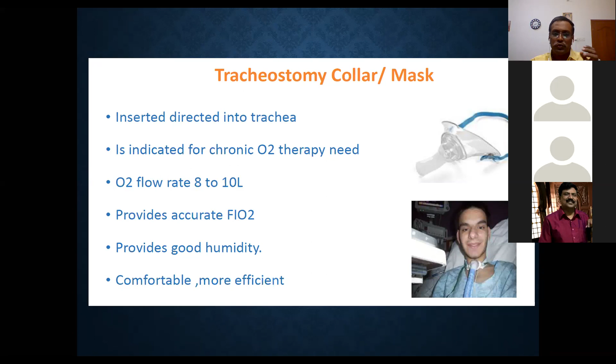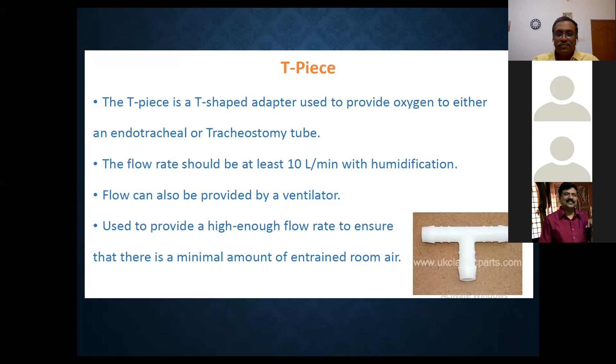And the next one is a T-piece device. We can use this in an intubated patient. Before extubation, we can give a trial of spontaneous respiration to assess the ventilatory effort of the patient and whether the patient is able to maintain saturation or not. It is one of the weaning modes for oxygen therapy. The T-piece is a T-shaped adapter used to provide oxygen to either the endotracheal tube or a tracheostomy tube with a flow rate of 10 liters per minute. Flow can also be provided by the ventilator or by the oxygen source. It is used to provide a high enough flow rate to ensure that there is a minimal amount of entrained room air.